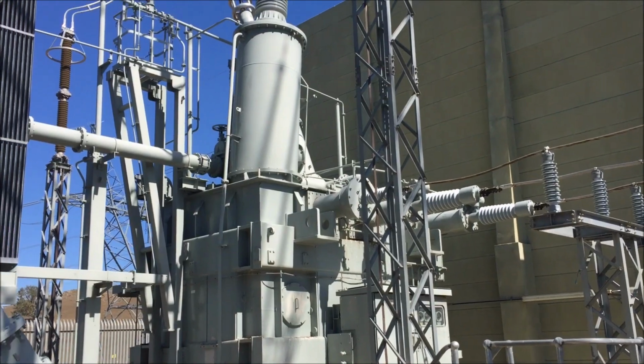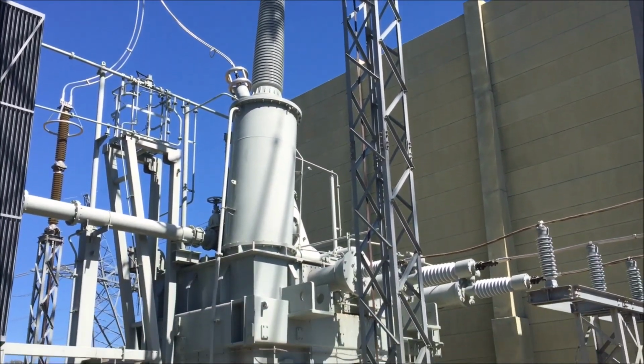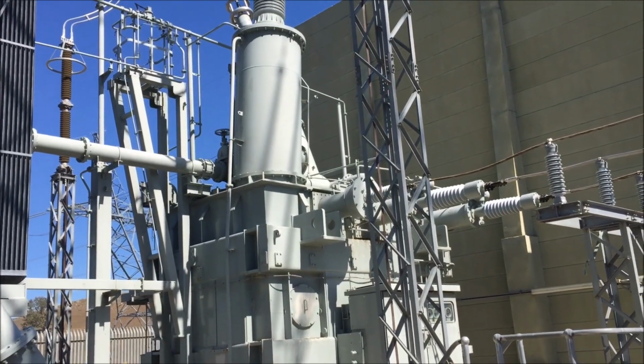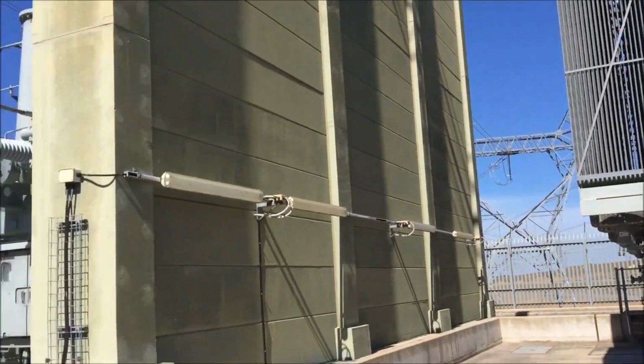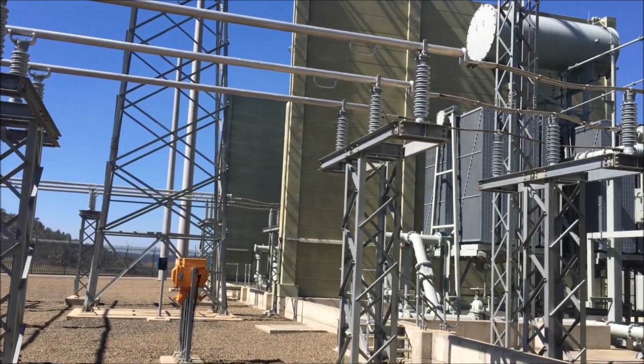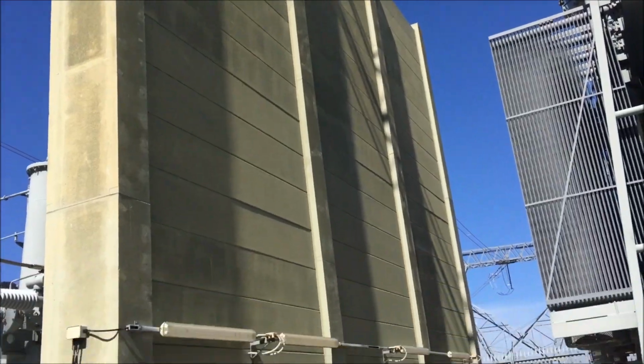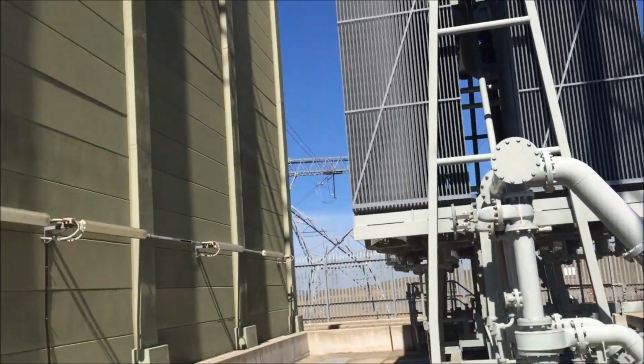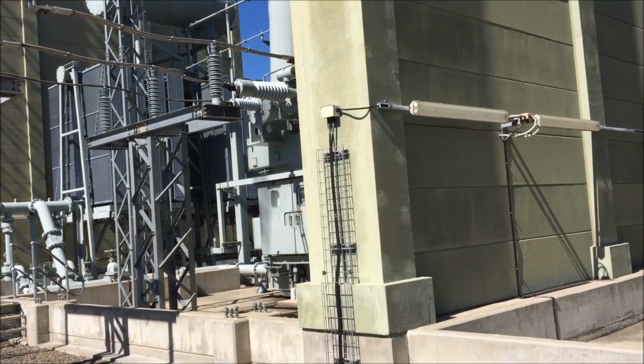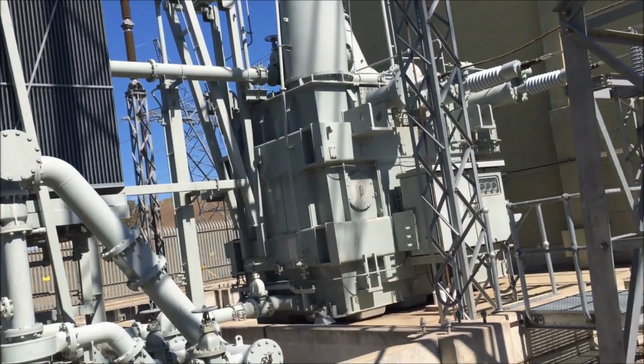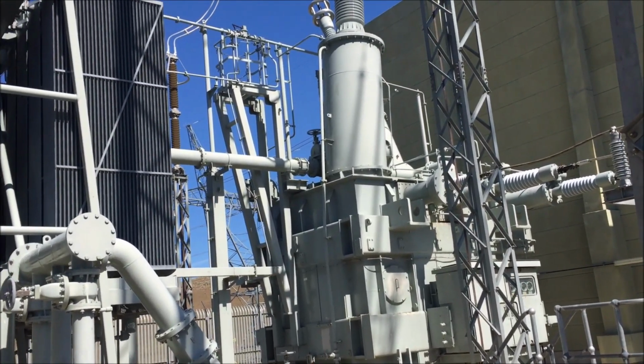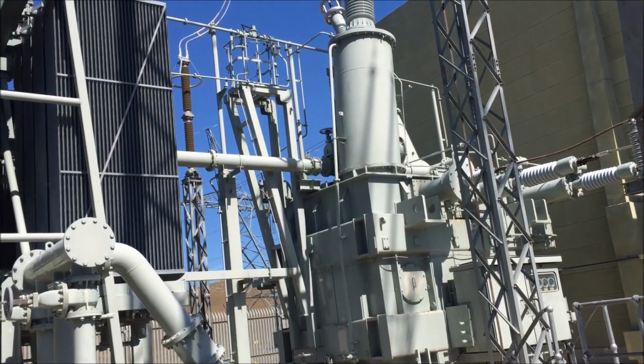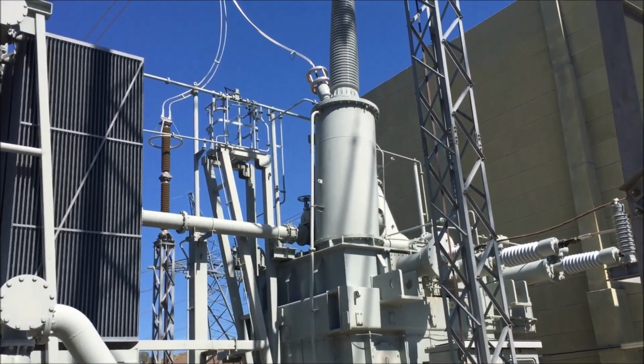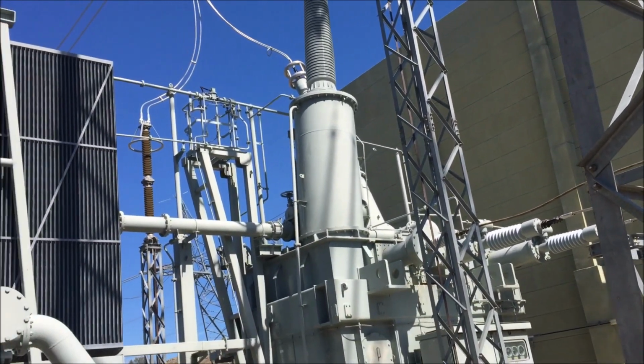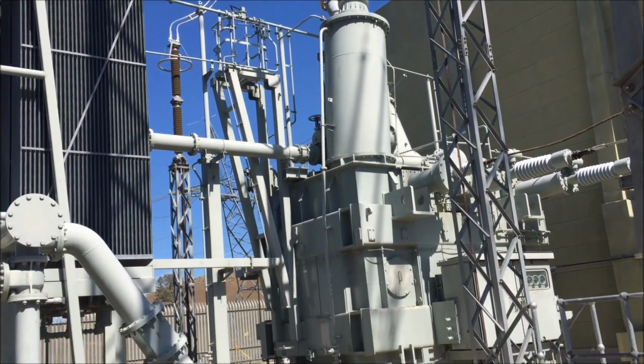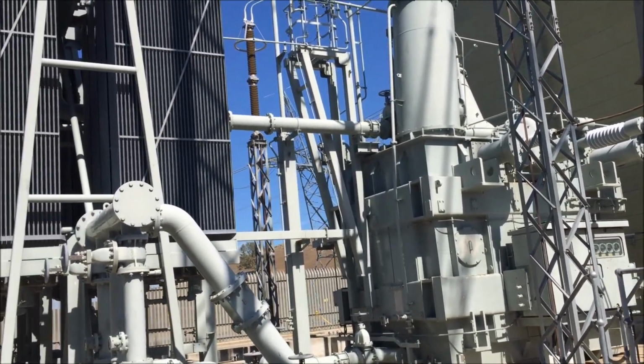Now we get to the business end of stuff. This is a single phase 500 to 330 kV transformer, and there are 3 of them. 1, 2, and the other one's up beyond the last wall. They have these big walls in between them, so if that fails and explodes, it doesn't take out old mate next door. They use single phase units because a 3-phase unit this size would probably weigh 500 tonnes. You just never move them, they're too big. So they split them into 3 single phase units, which also has the advantage, like I said, if one blows up, you just replace that single phase and you don't have to replace the whole unit.